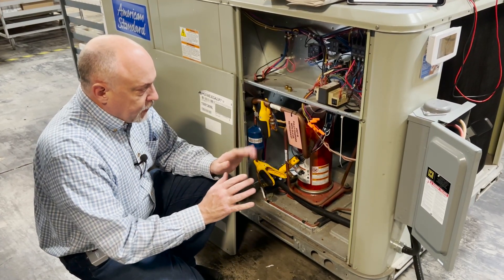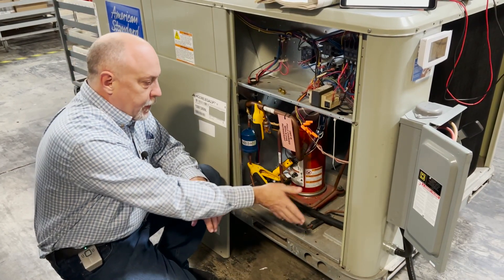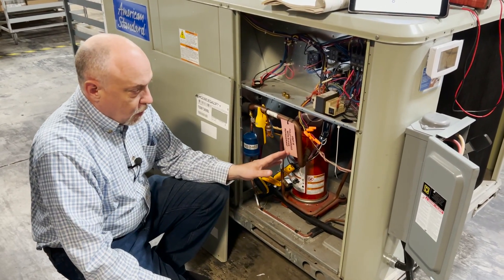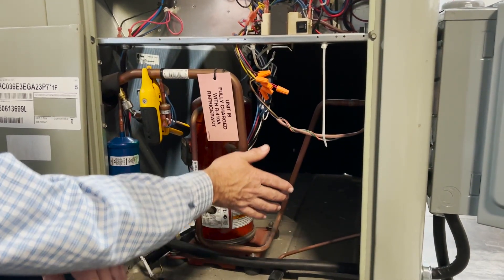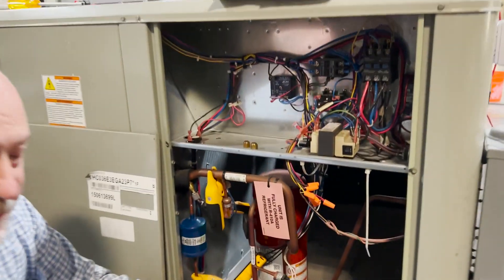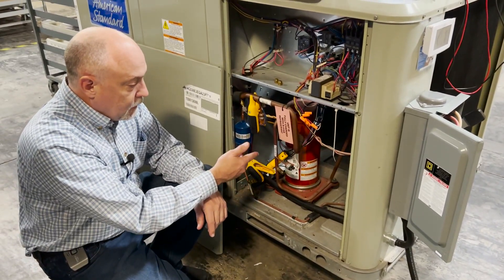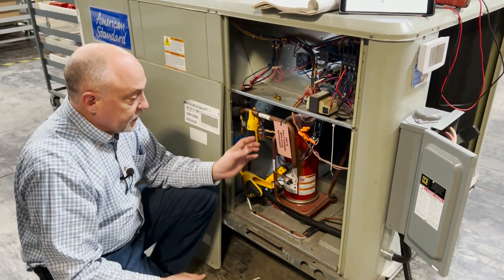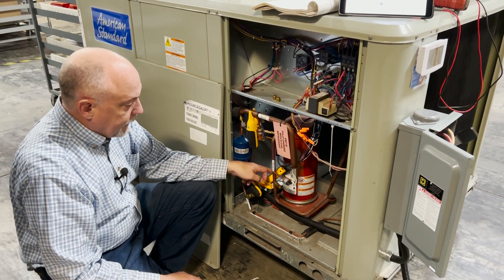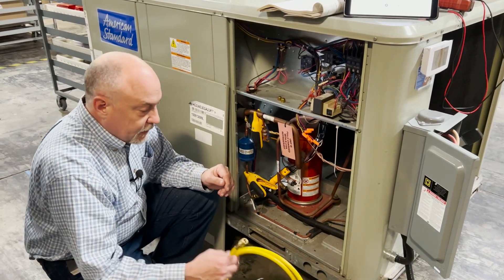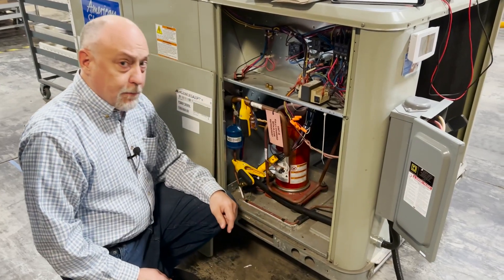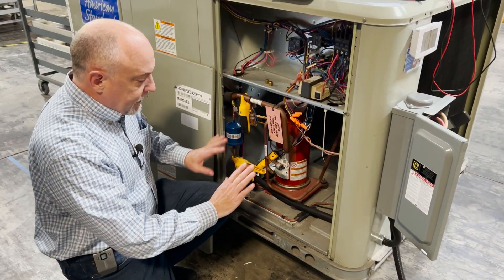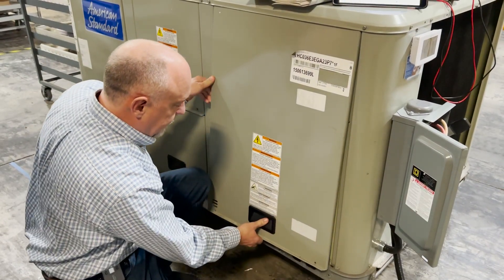First thing you'll notice when you work on a package unit like this American Standard or Trane unit, we have this wide open hole here that goes into our condenser. When we're doing our testing, we want to make sure that air does not enter through the compressor compartment because that's going to drive the head pressure way up. It's going to bypass the condenser instead of going into the coil. So what we want to be able to do is put the door on. These smart probes are really slick because I can have the suction line, liquid line, the high and low pressure hooked up here. If I was going to add charge in, I'd just run a single hose into the machine with a charging T and run out one of the side ports here on the unit. I can get everything inside here where I need to make my measurements, and then I can go ahead and throw this door on here before I start the unit.